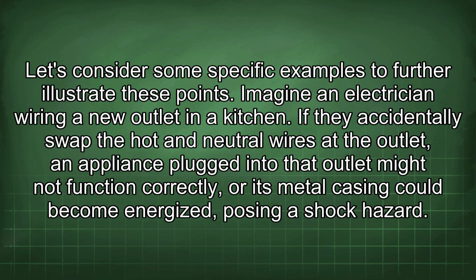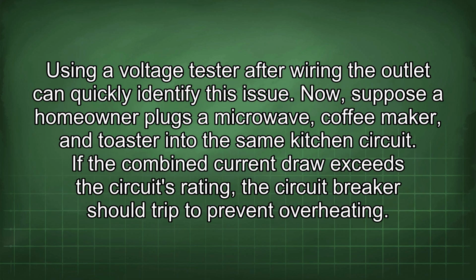Let's consider some specific examples to further illustrate these points. Imagine an electrician wiring a new outlet in a kitchen. If they accidentally swap the hot and neutral wires at the outlet, an appliance plugged into that outlet might not function correctly, or its metal casing could become energized, posing a shock hazard. Using a voltage tester after wiring the outlet can quickly identify this issue.